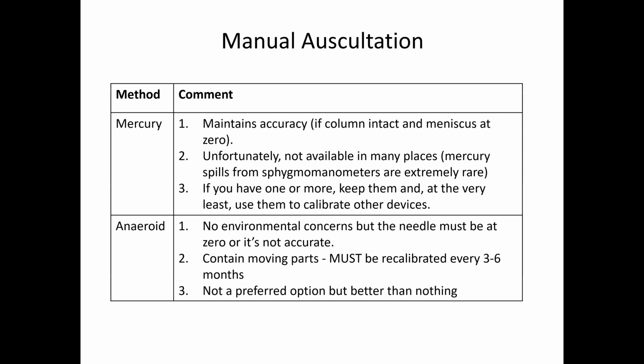And the reason why I'm a big proponent of mercury is because if the column is intact, and I would hope people would notice when it's not, if the column's intact and the meniscus is at 0, really it maintains its accuracy. You don't have to do anything else to it. And then the second reason why mercury is so useful is if you're going to do any calibration, which I mentioned at the start and I'll mention later, then you really need a mercury if you're in an LMIC setting. Otherwise, you'll have to purchase an electronic calibrator, and those devices are super expensive, thousands of dollars.